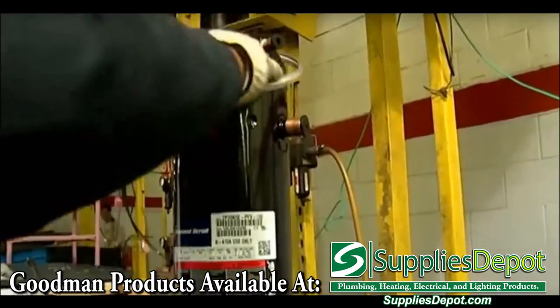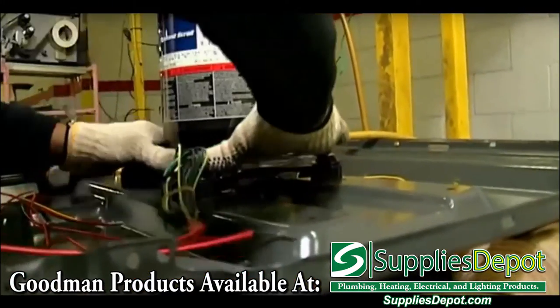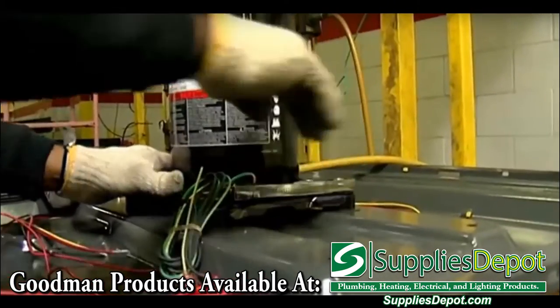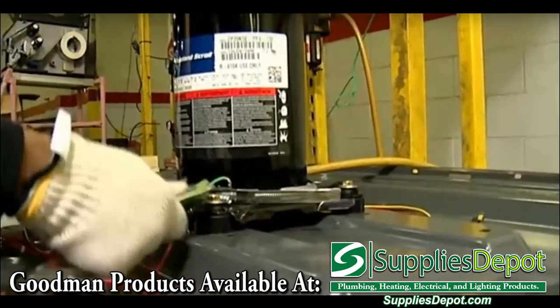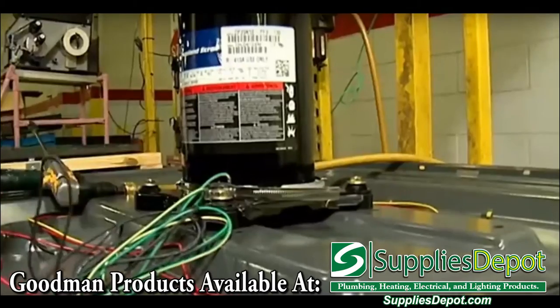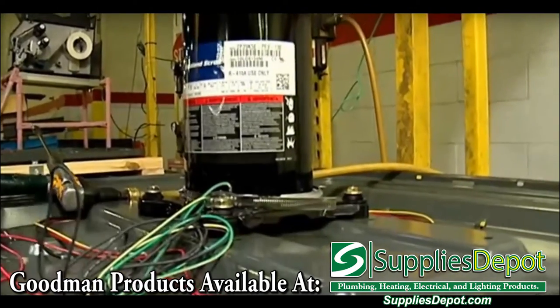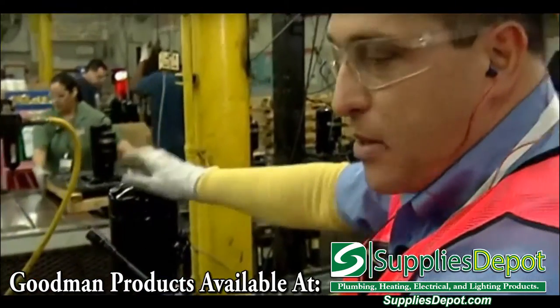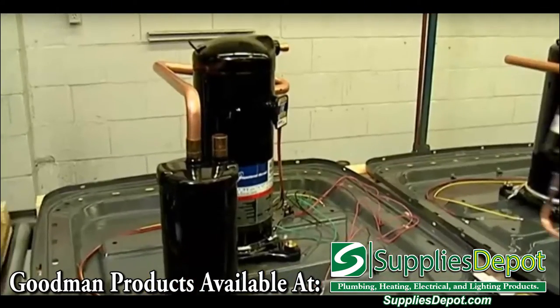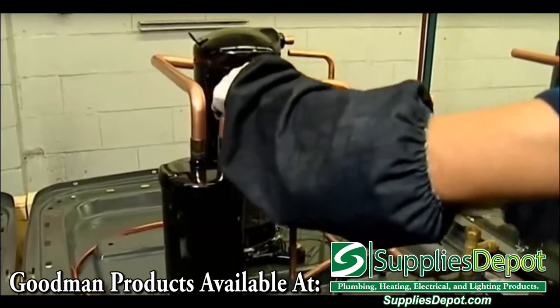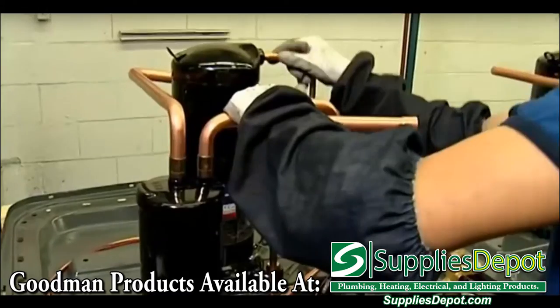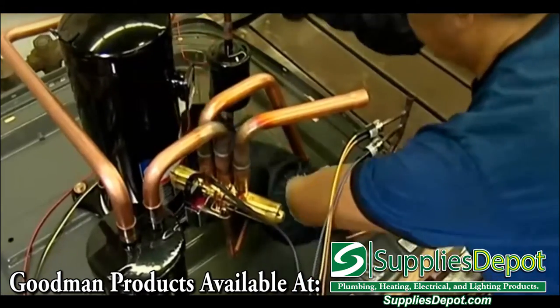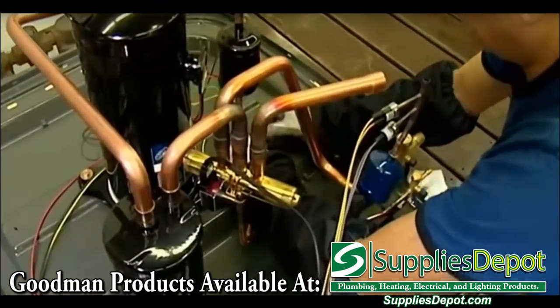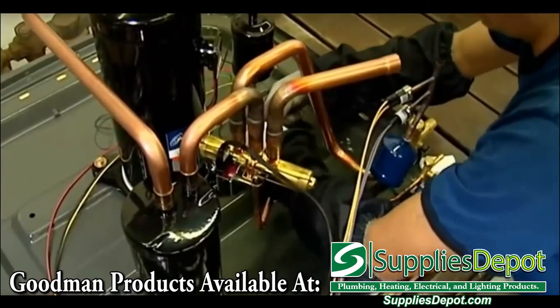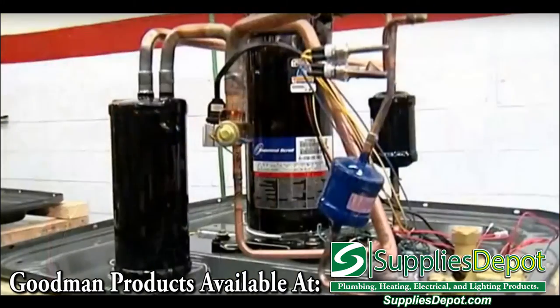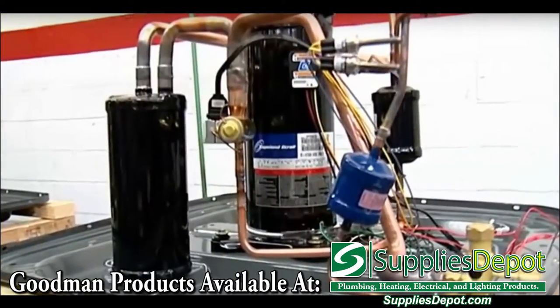We also went in and put a heater band. If you look in here, you will see you have a heater band. And the whole purpose of the heater band on the compressor is to make sure we don't have any liquid going into the compressor, because that will create slugging and that will kill the compressor. We also went in and put a time delay kit on the heat pump, and the whole purpose behind it is to ease the noise and make sure the shifting is very, very smooth when the heat pump shifts back and forth, especially on the reversing valve.